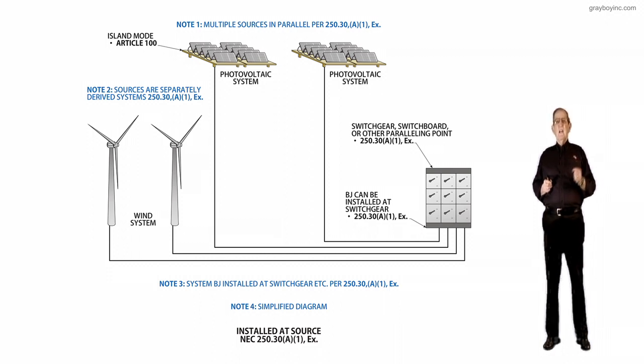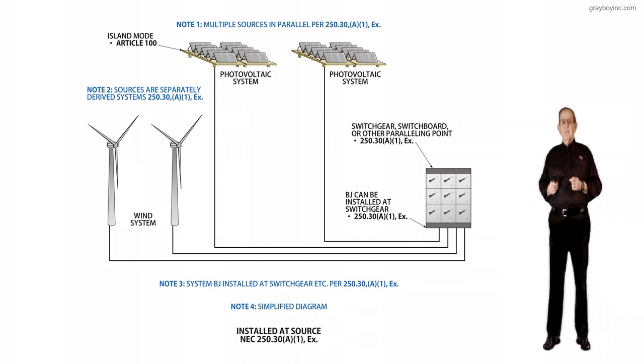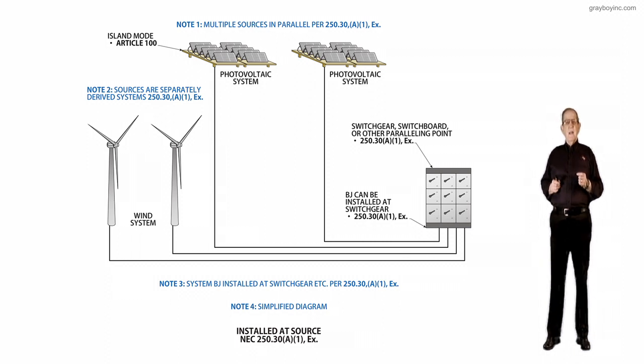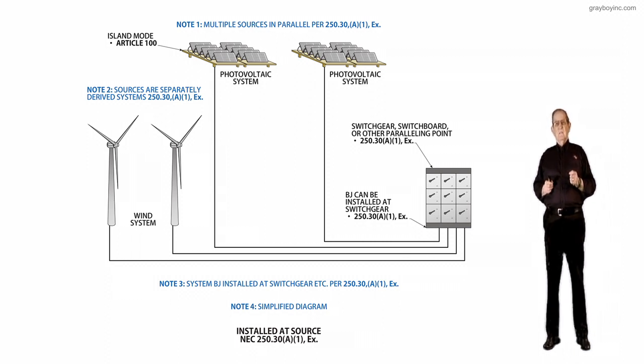Many times, like with engine generators, fuel cells, or inverters, each equipment is supplied with a main disconnect, and that would then require the system bonding jumper for system grounding at each source.